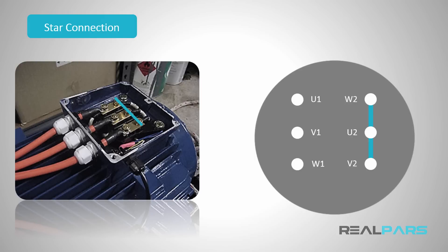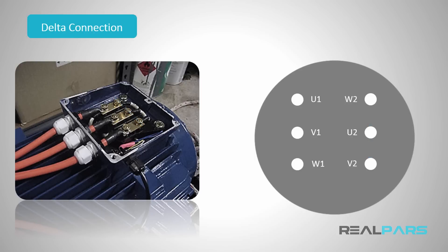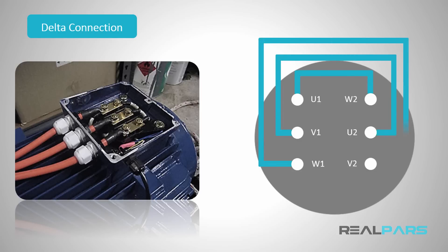Now, if you want to start the motor in delta connection, just like you've learned before, you can connect U1 to W2, V1 to U2, and W1 to V2.